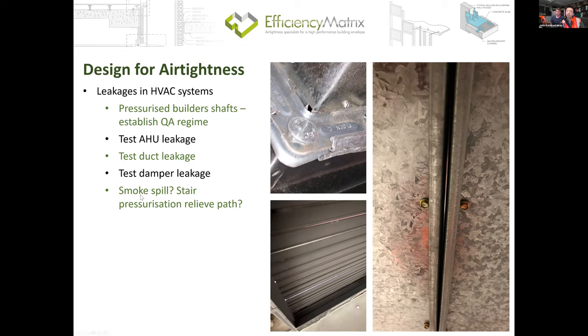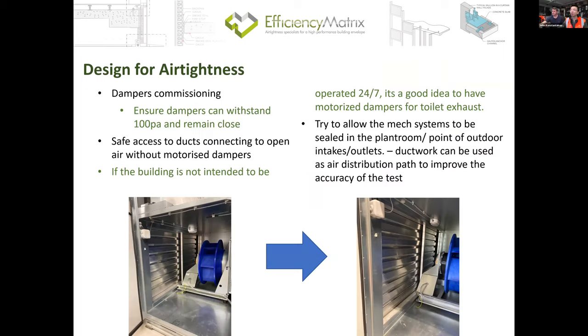The other is smoke spill and stair pressurization relief paths, because sometimes when we see some of those pressure relief dampers in the ceiling space connecting to the facade, some of them only have butterfly dampers, which have a 10 mil gap all around them, leaking air in and out day and night, which is totally unacceptable. Okay, these are some suggestions that would make life easier and make it easier to achieve a better test result.